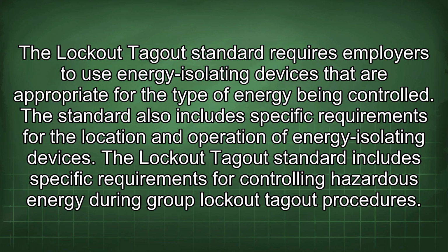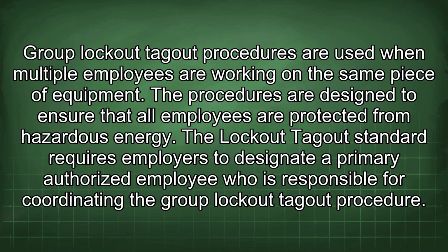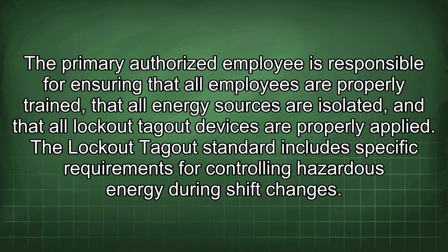The Lockout Tagout standard includes specific requirements for controlling hazardous energy during group Lockout Tagout procedures. Group Lockout Tagout procedures are used when multiple employees are working on the same piece of equipment. The procedures are designed to ensure that all employees are protected from hazardous energy. The Lockout Tagout standard requires employers to designate a primary authorized employee who is responsible for coordinating the group Lockout Tagout procedure. The primary authorized employee is responsible for ensuring that all employees are properly trained, that all energy sources are isolated, and that all Lockout Tagout devices are properly applied.